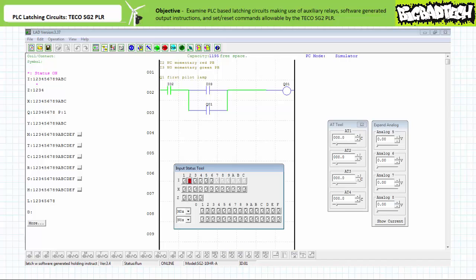Using the TECO SG2 client programming software simulator utility, let's examine the behavior of this program. The simulator's default start state assumes all switched inputs are normally open, so before initiating simulation one must toggle the simulated field input device attached to input 2 to closed. In the deactivated state, the make instruction examining input I2 permits logical continuity; however, the make instruction examining input I3 does not permit logical continuity onto output Q1. The make instruction examining Q1 in rung 2 also does not permit logical continuity, and output Q1 remains de-energized.